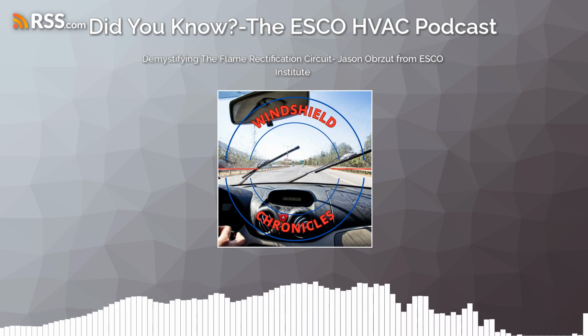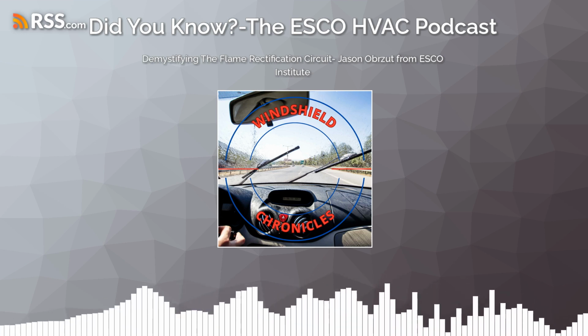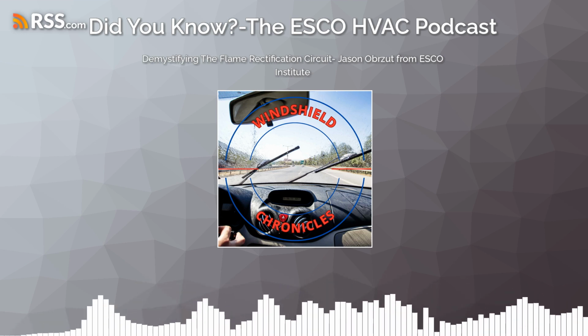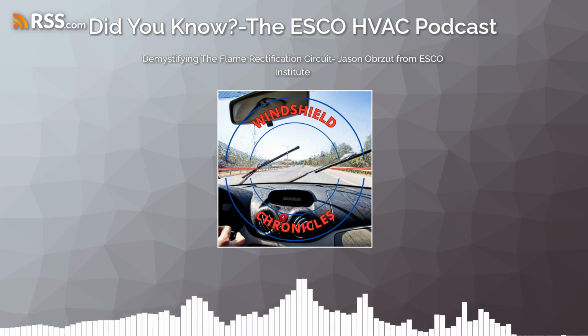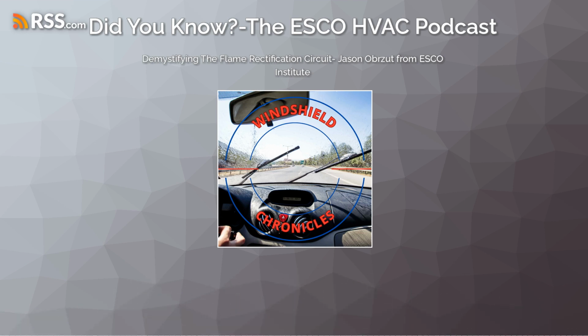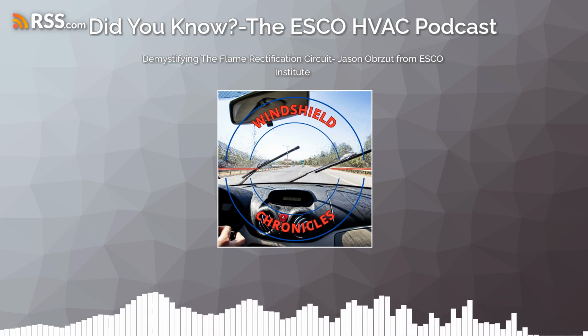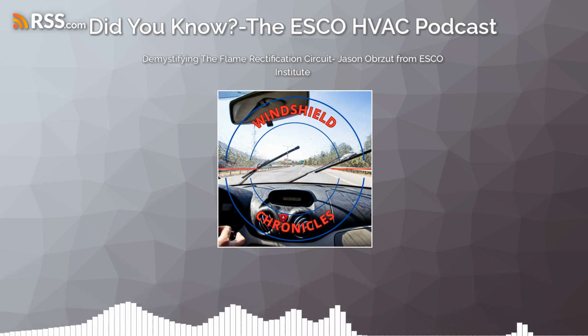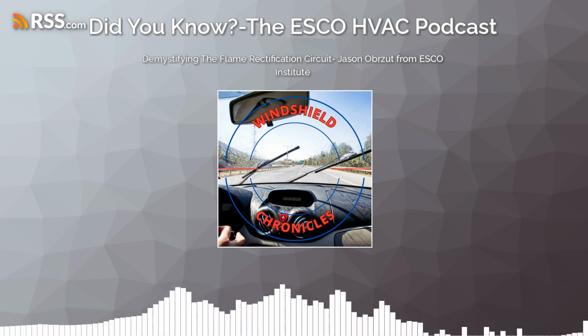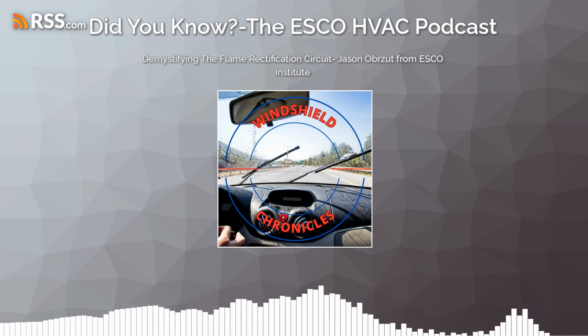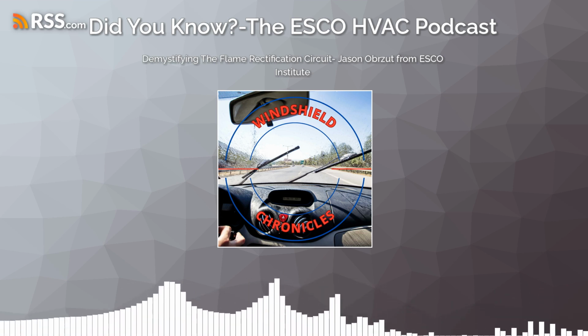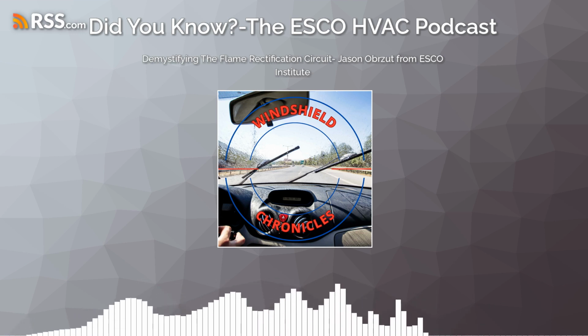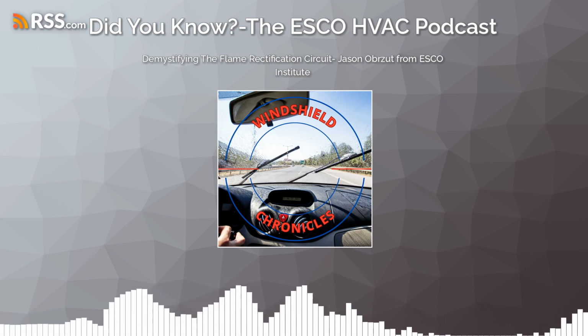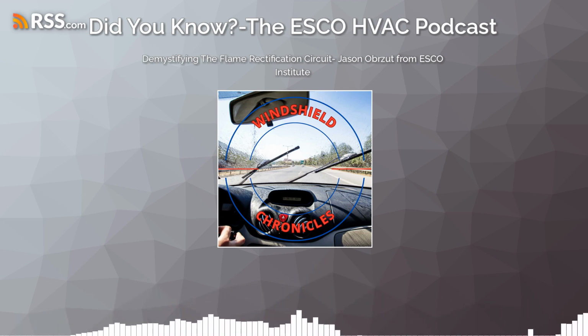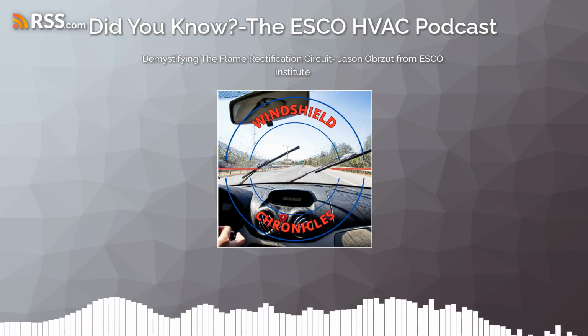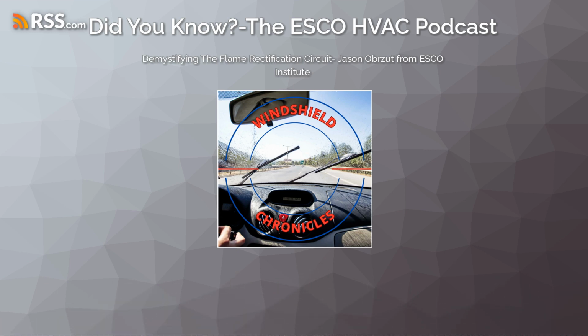Well, what if we need more? What if our valve is larger and we're talking about a commercial gas valve or an industrial gas valve that's got a bigger diaphragm and a bigger solenoid and we need more power? Well, we just take thermocouples and we put them in series and we create more voltage. That's all it is. So we're applying heat onto multiple thermocouples so that we get a common higher output voltage. Works great when we're talking about a larger gas valve, right?